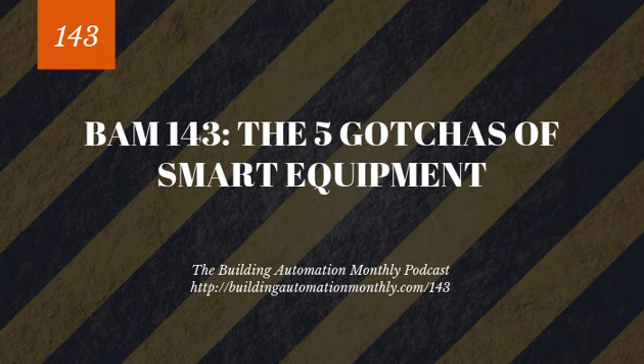You can have a lot more forgiveness when you mess with temperature, but when it comes to flow, you can really hose some things up pretty fast with some just minor changes on CFM, especially if you're dealing with large systems. Okay, so then with all of that being said, we have to think about gotcha number 4, which is system segmentation. And I see this quite often. And folks try to solve the sequence alignment and the design accuracy problem by segmenting portions of the same system. This is a recipe for frickin' disaster.